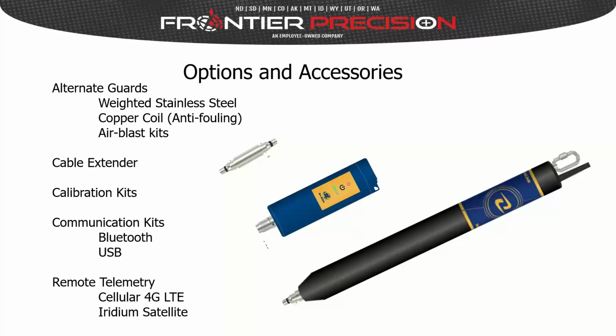Now, in a previous slide, I mentioned that there were 10-meter and 30-meter cable options for this. If you need to extend those, we have this cable extender that can pop in the top of this. This is a waterproof connection. And then on the other side, you can get whatever length of cable you want, up to about 4,000 total feet. We have some calibration kits that consist of a little air compressor and a bubbler situation, so you can create a water-saturated-with-air, 100% environment.